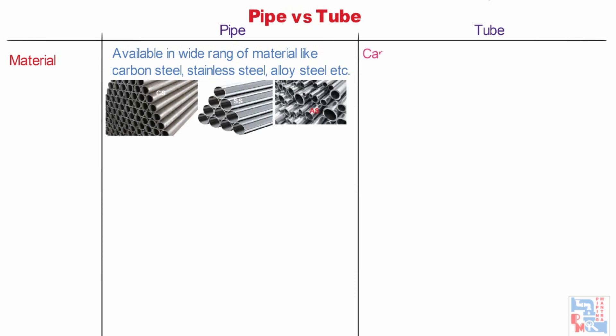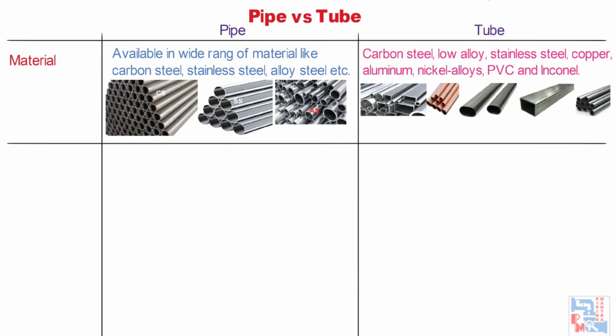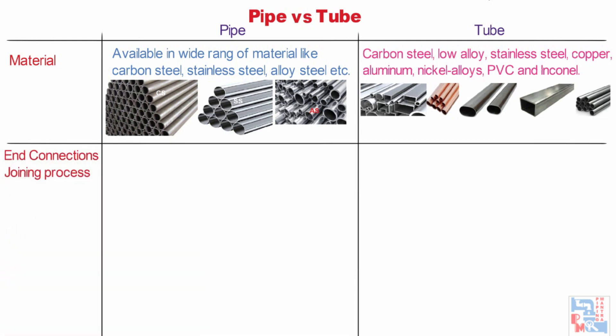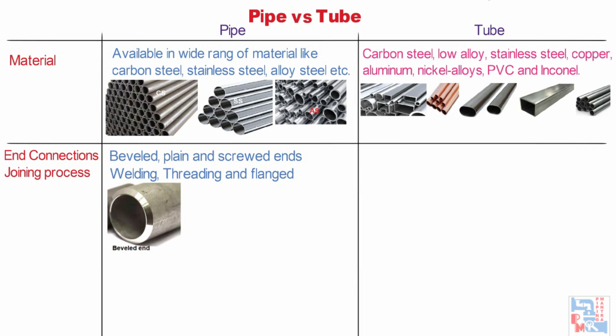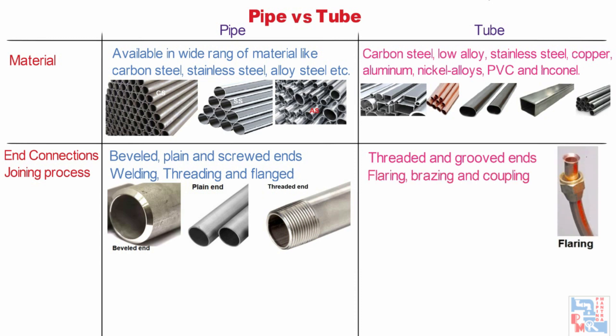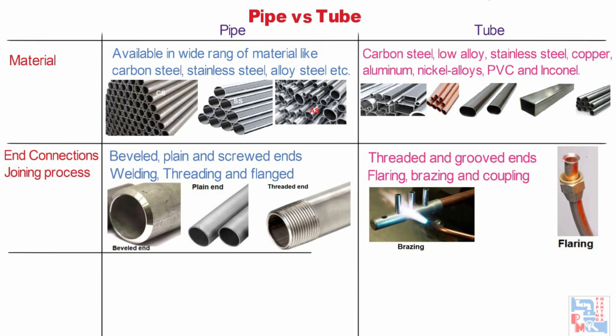For tubes, the materials available include carbon steel, low alloy, stainless steel, copper, aluminium, nickel alloy, PVC, and Inconel. Now let's discuss end connections and joining processes. For pipe, the most common end connections are beveled, plain, and screwed ends — with welding, threading, and flange connections being very common. For tubes, threaded and grooved ends are available for quicker connections, with flaring, brazing, and coupling as joining processes.